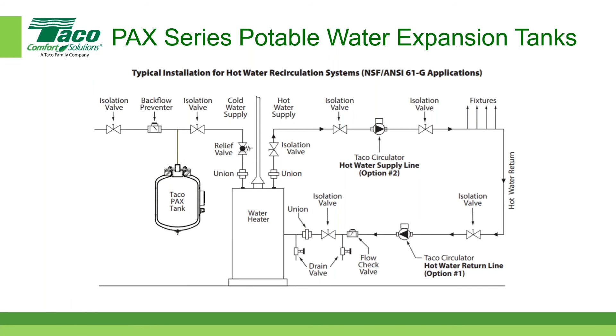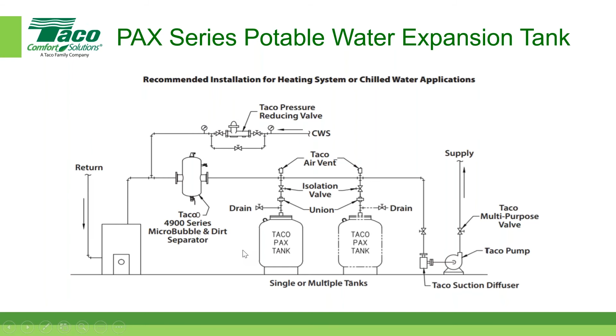Here's a recommended installation for heating system and chilled water applications for the PAX tank. It's installed just like a CA tank or the CBX - well, not the CBX since that has a bottom connection, but like the CA tank. Here's a picture of the expansion tank, the CX, the Taco model CX tank, the diaphragm style tank.